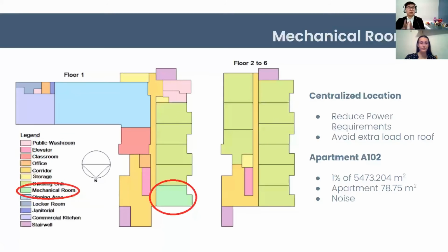And to that extent, if we look carefully at the actual figure that was provided in Gabby's last slide, we would notice that the actual mechanical room is located on the first floor of the building. This being a central location that we're looking after in order to minimize the size of the duct, pipe, and conduit runs, and thus help reduce the power requirements for pumps and fan motors. A minimum of 1% of the building's gross area would need to be provided for the mechanical room. And in this case, the size of it is 78.75 meters squared, which is much greater than the 54.73 required.